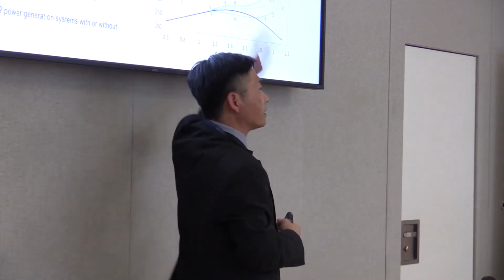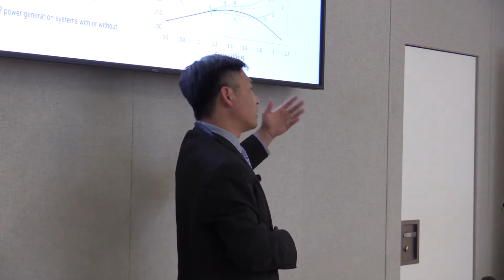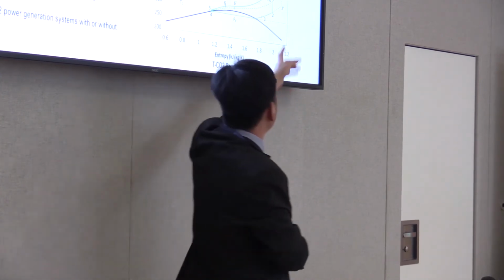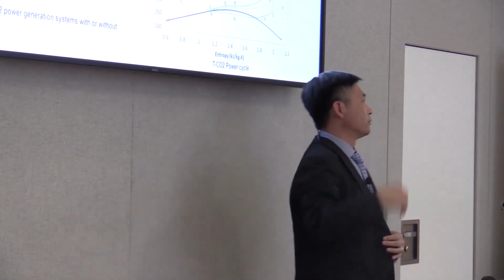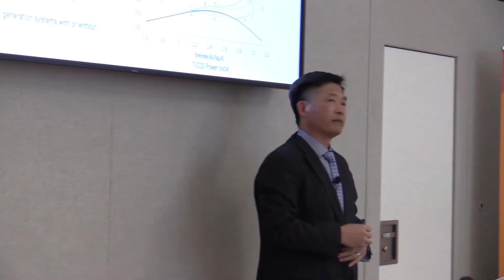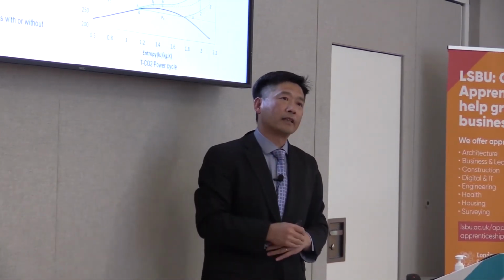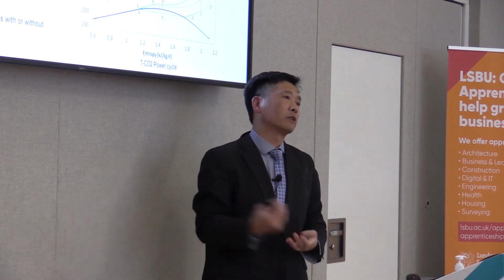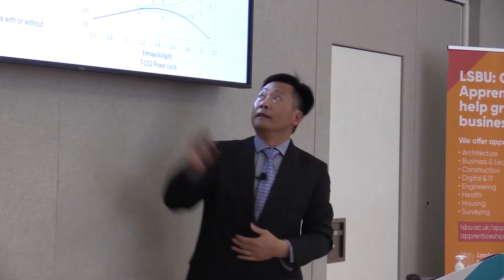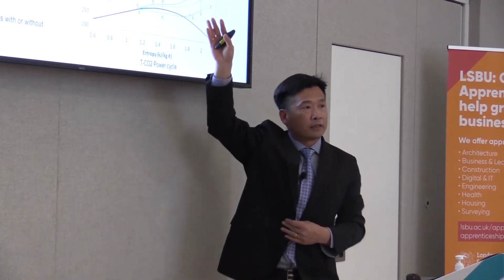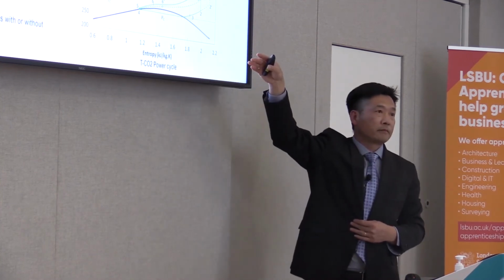It can be higher, 120 bar, 140 bar, and the temperature, no limitation, whatever, as long as it's less than 2000 K. So no limit for the transcritical CO2. So you can specify the operating conditions for both systems.